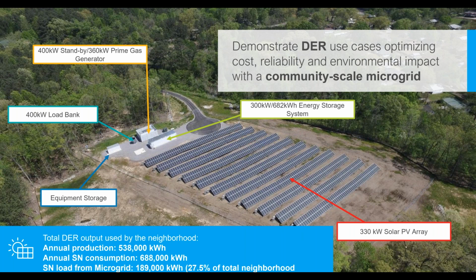So why did we design a 330 kilowatt solar PV array? The key reason here is that for the smart homes, the expected peak load is about 250 to 300 kilowatts. So with a 330 kilowatt solar array at peak, the solar should be able to carry the entire smart homes and export to the grid. And that's at peak. But the average consumption is about 50 to 70 kilowatts. So the solar during the day is typically carrying the entire load and then exporting to the grid.